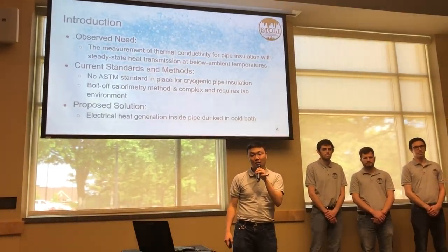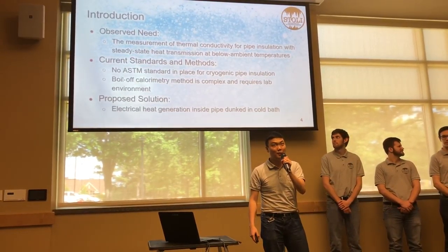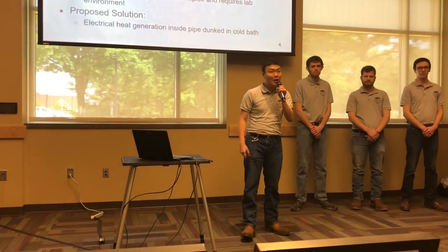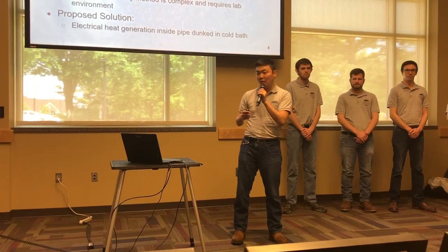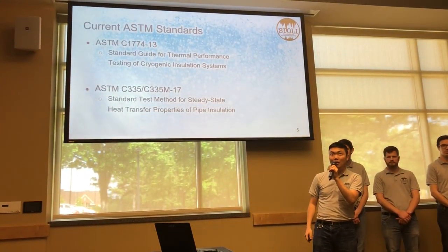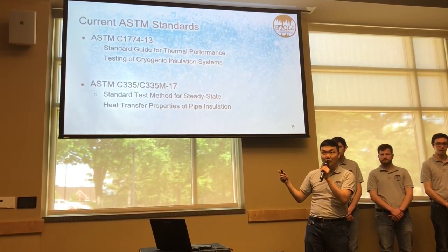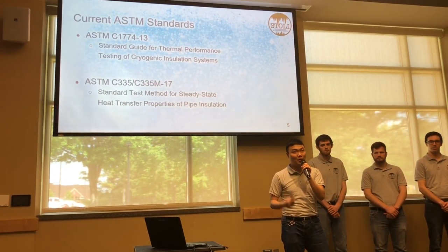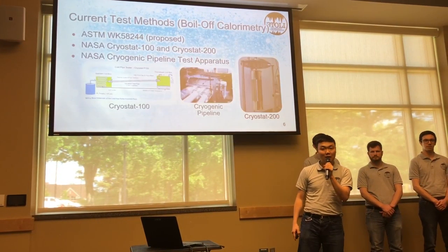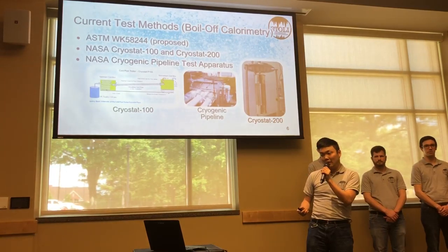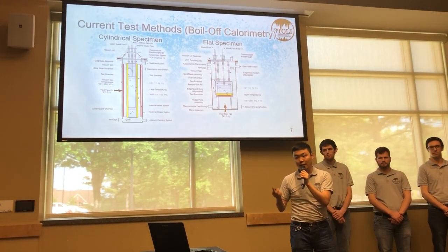The objective of the project is to find the thermal conductivity of low-temperature pipe insulation. We don't have current ASTM standards for cryogenic pipe insulation. There are two main standards we can achieve: one for cryogenic insulation and one for pipe insulation. NASA created two types of boil-off calorimetry — a cylindrical specimen and a flat specimen.